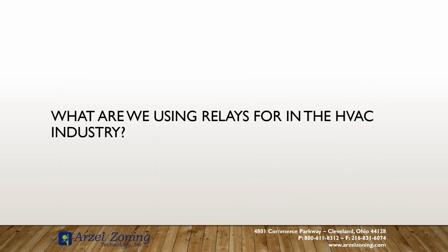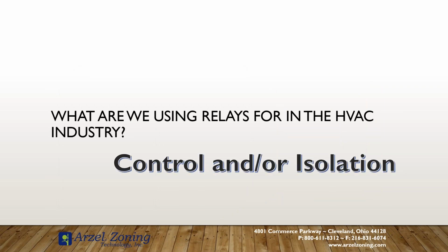So I've kind of answered this one already. What are we using relays for in the HVAC industry? And the thing that we use relays for is control and or isolation. So the control side of things allows us to have multiple things happen, multiple events, multiple conditions. Then as those conditions are fulfilled, the equipment's allowed to continue operating.